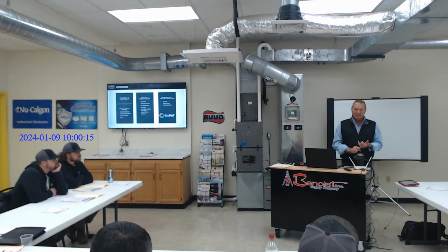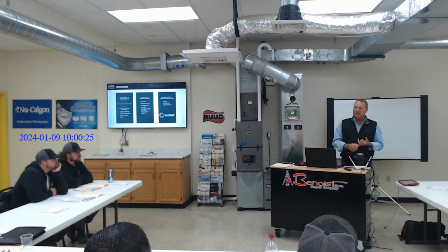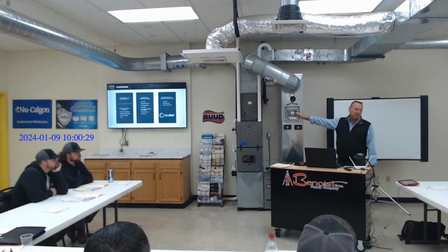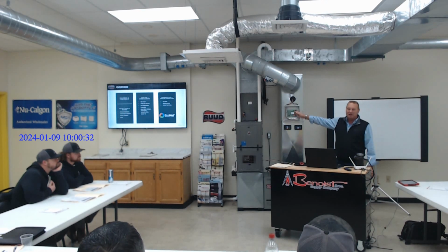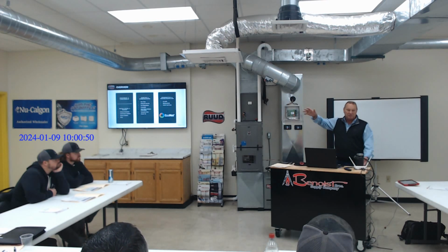Nobody knows this. And this is where we're really running into problems with 90% furnaces and zoning. You need 150 to 160 CFM for 10,000 BTUs of heat. So guess what? If I put an 85,000, 96% furnace in, do the math. Okay, do 160 times 8. I need almost 1,300 CFM to keep that furnace from tripping on limit. Because you know what the limits are set at in these furnaces today? For all the old school guys that used to 200 and 180, some of these limits are 120, 130. They won't tolerate any more temperature rise than that, and you're tripping limits. You do that 3 times in a cycle, we got issues, okay?